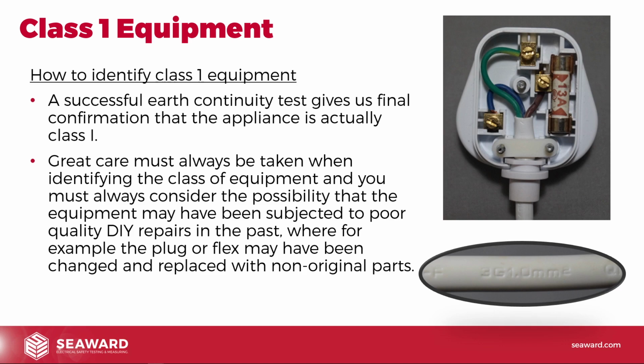Somebody could have come along, and I've seen this in real life, where somebody's only got 2 core flex and they've just used 2 core flex instead. So you look at it and say, oh yeah, it's Class 2, and actually it isn't Class 2. It's been bodged in the past, and you're coming along and assuming it's right. So always be on your guard a little bit. Is this original? Has somebody come along and changed the whole flex on here and just left the earth out?